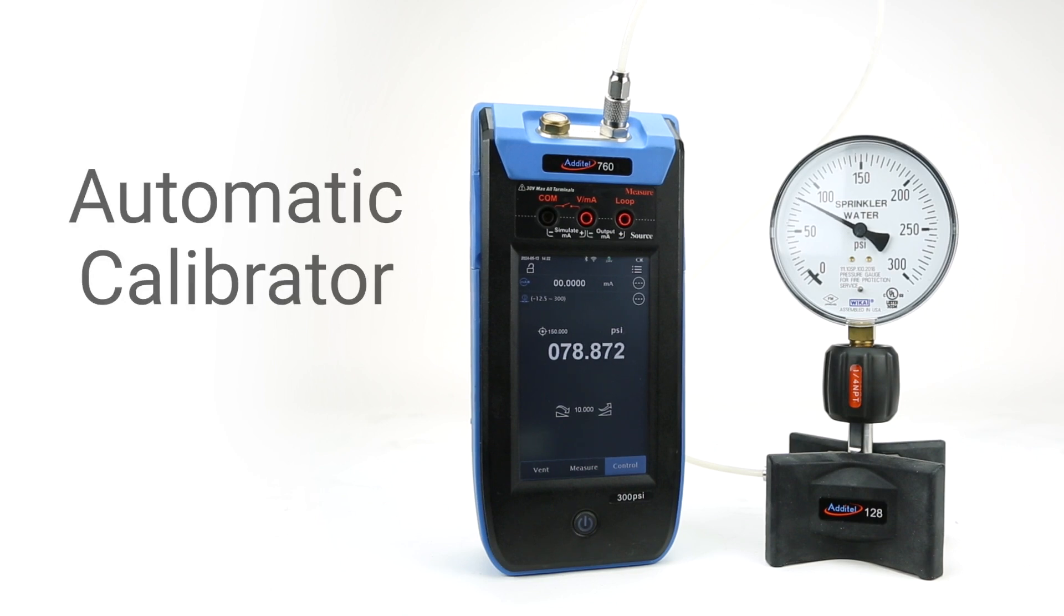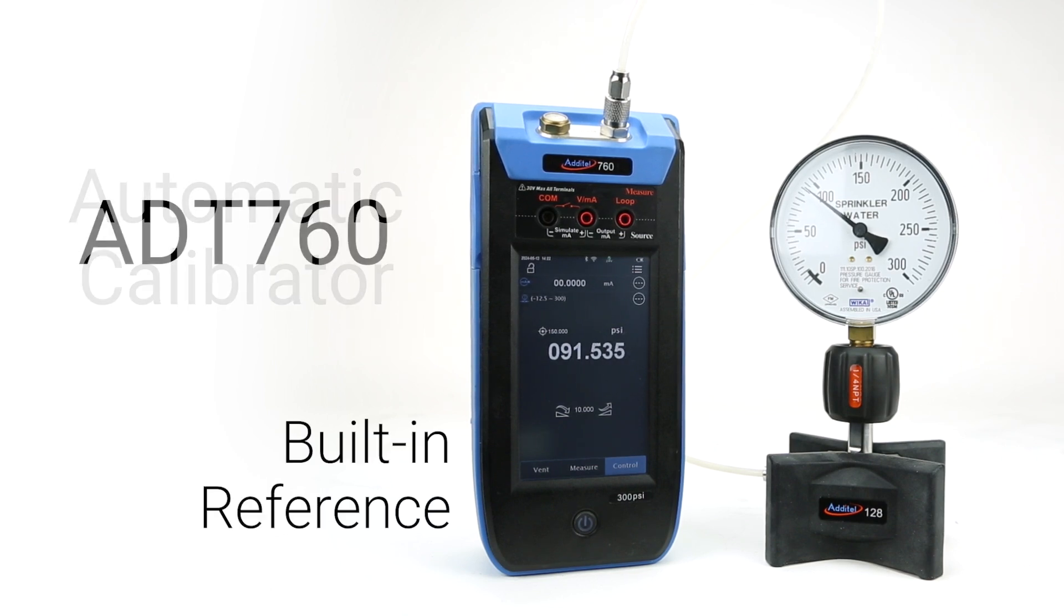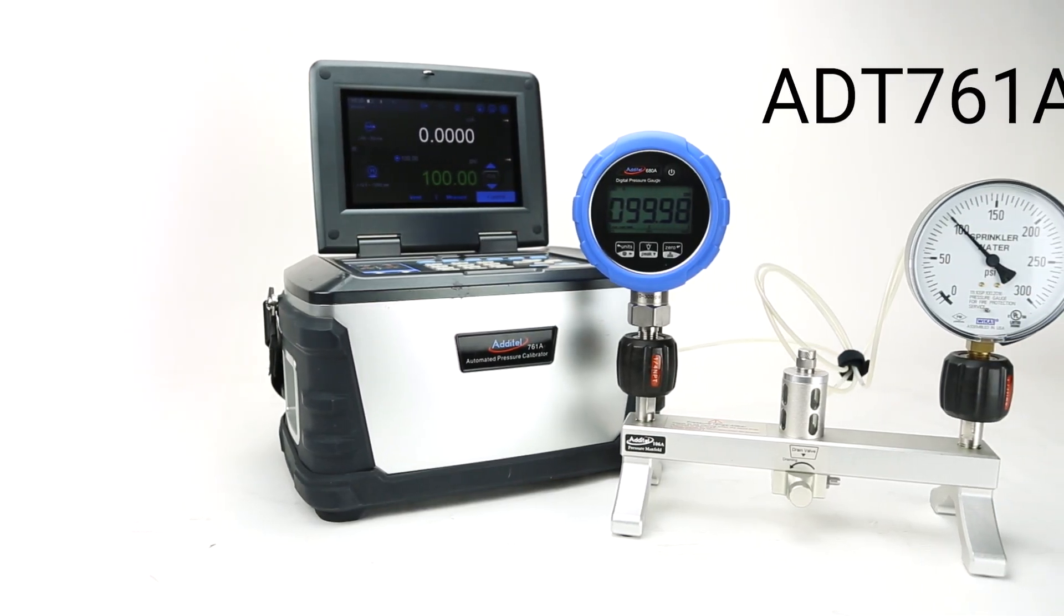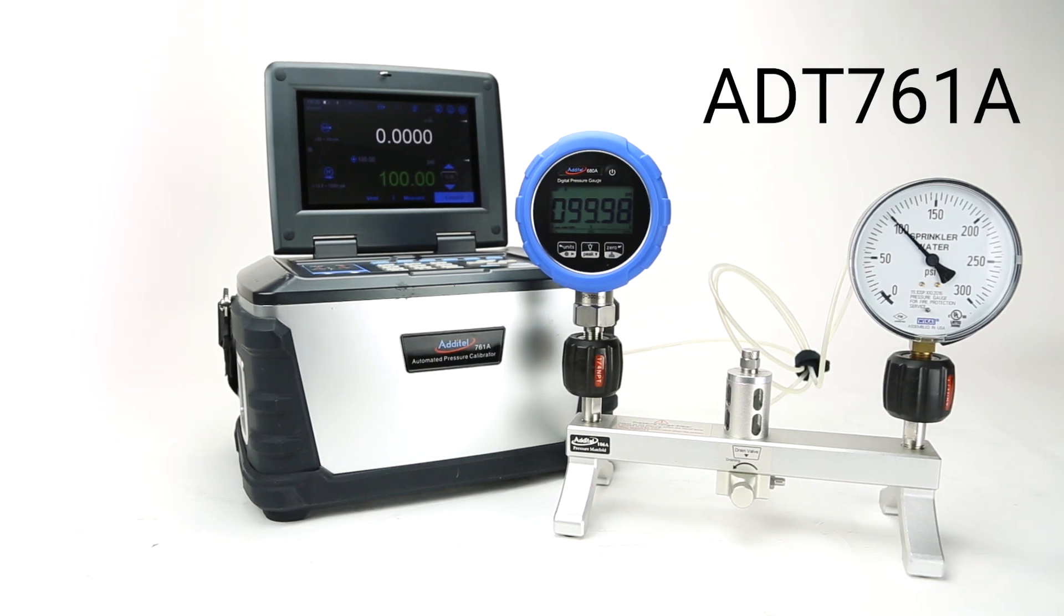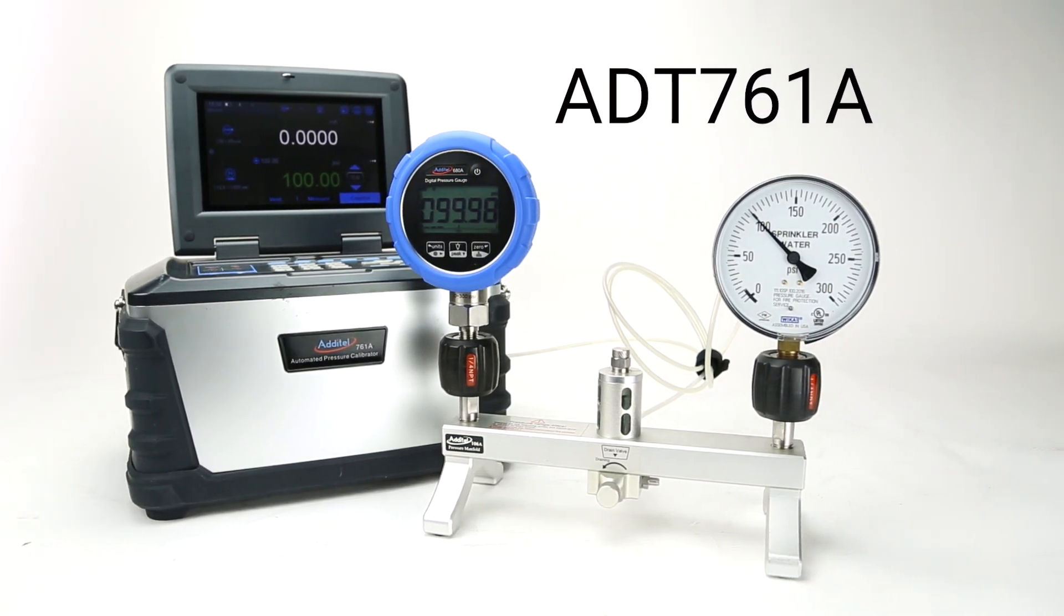Lastly, it could be an automatic calibrator that both includes a reference standard and generates its own pressure, like an Additel 760 or 761A. Although these options are more expensive than a reference gauge and manual pump, it's important to weigh in the time cost of using manually operated tools versus using an automatic calibrator, especially when calibrating multiple devices.